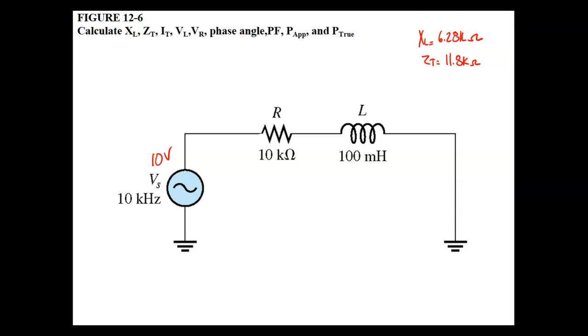So anticipating what you're supposed to see, that's the name of the game in troubleshooting, guys. Have a fairly good idea of what you're supposed to see before you put your test equipment in there. So we don't like to make measurements to make measurements. We like to make measurements to verify what we think's there. Now, if it's not what we anticipate, either we got a problem or we figure out we did something wrong.